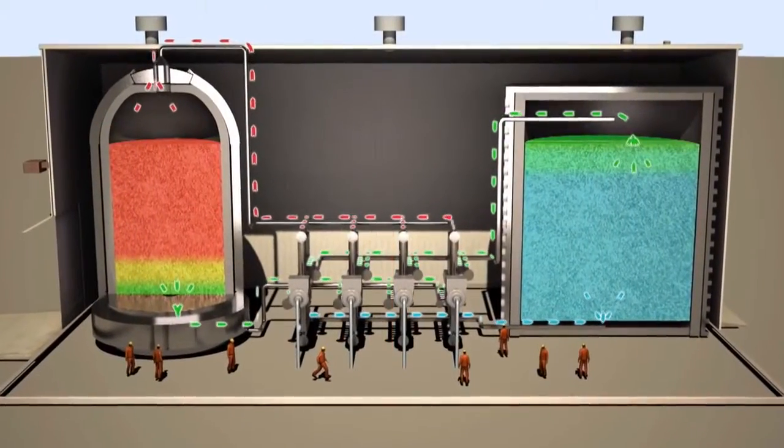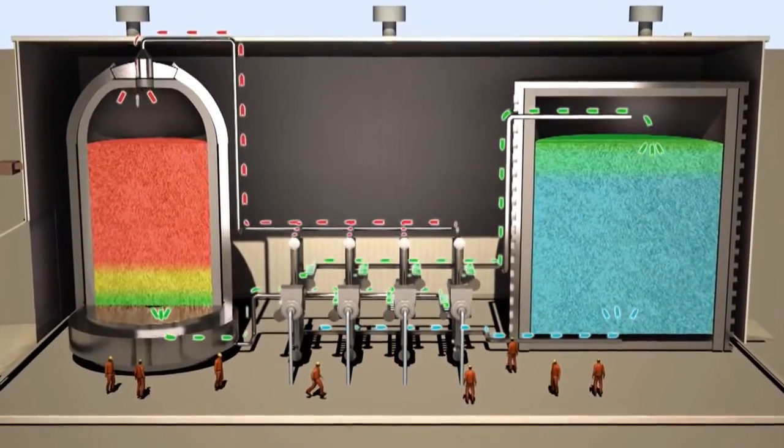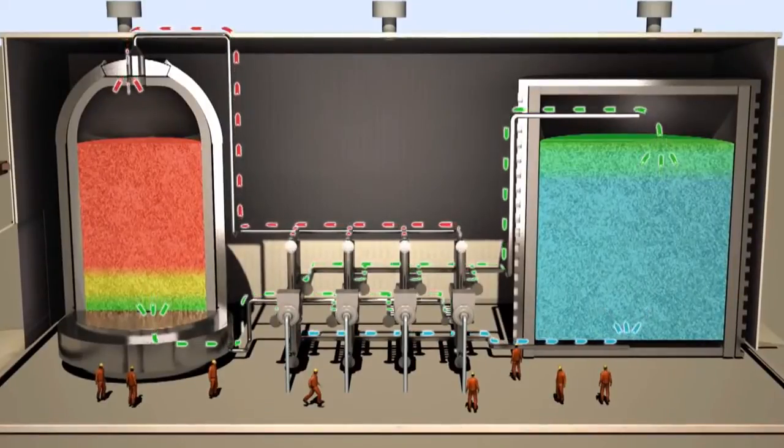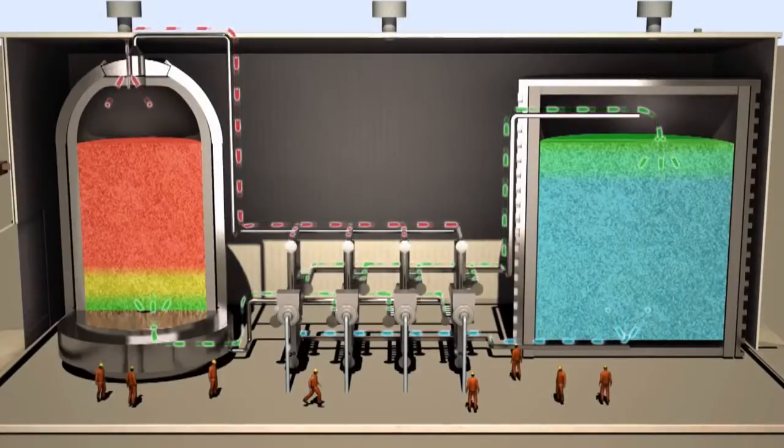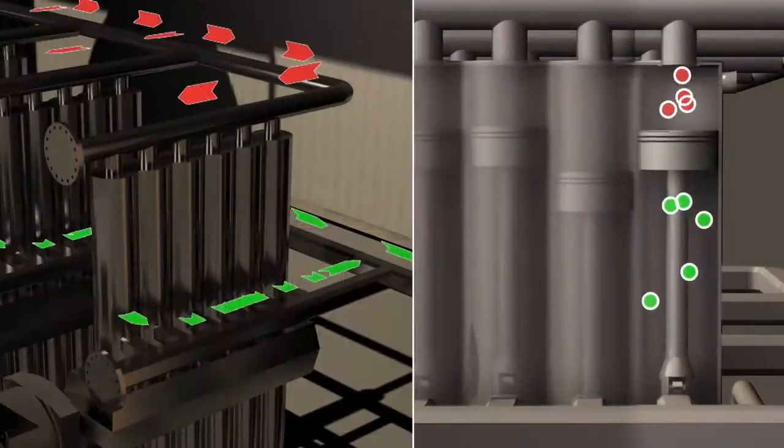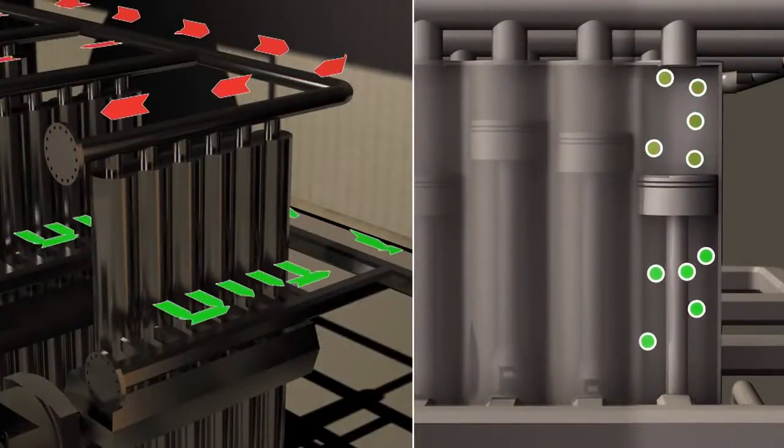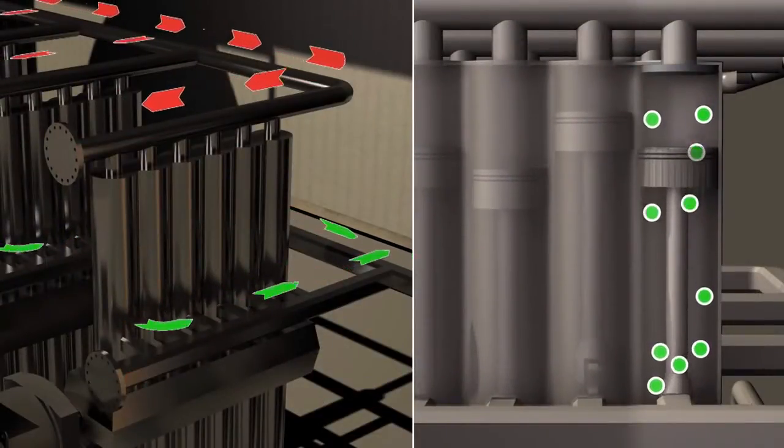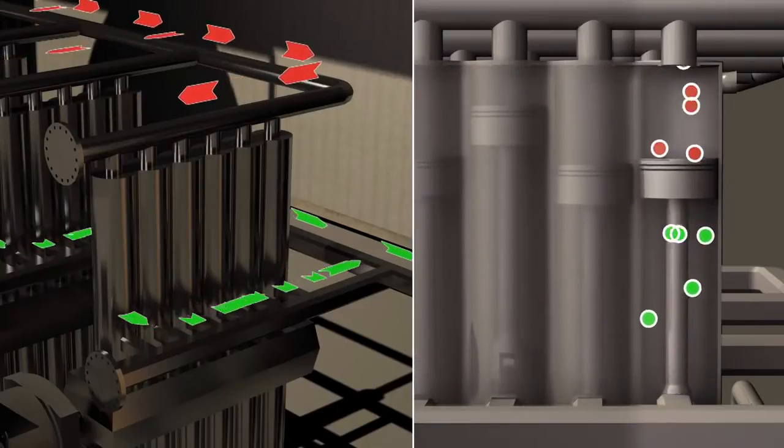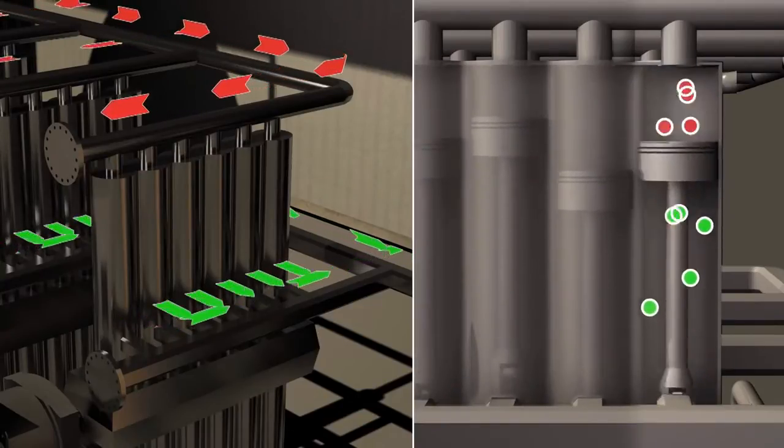At any time during the charging cycle, the system can be reversed to start the discharging cycle and release the stored energy. This is done while the engine continues to turn in the same direction. The valve timings are changed and the gas begins to flow in the opposite direction, a process which only takes about one second.